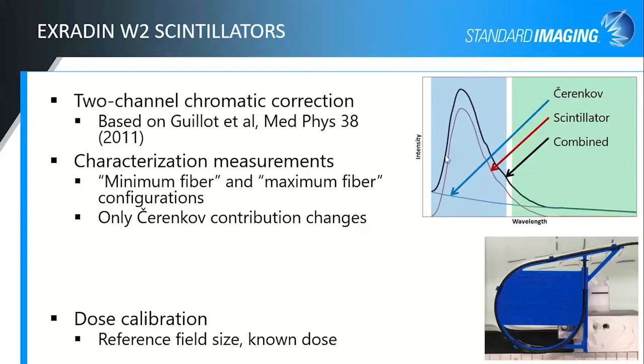So here it shows just a kind of rough plot of what our blue scintillator scintillation curve looks like. Cherenkov is a broad spectrum light, and so what we're really measuring is the combination of those. But we split the spectrum into 2 portions, a blue portion of the spectrum and a green portion of the spectrum. And we have you do 2 characterization measurements. This is an image or a picture actually of the bracket that we have for the water tank for doing those Cherenkov measurements. You would do a minimum fiber configuration with the fiber coming straight out of the field, and then a maximum fiber configuration measurement with the fiber wrapped around and coming across here.